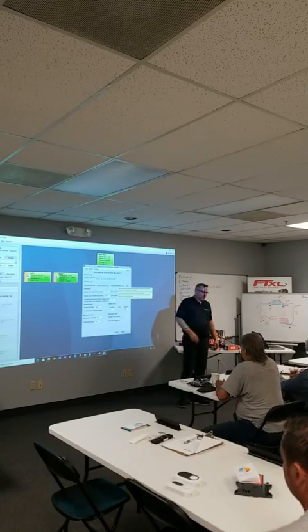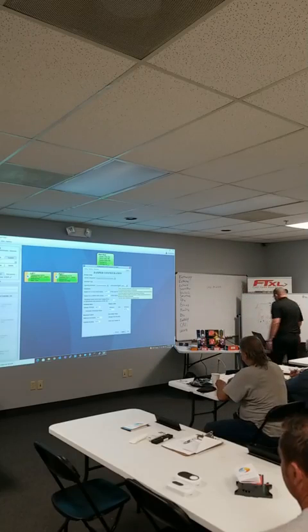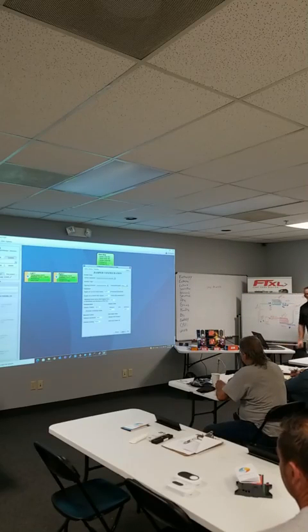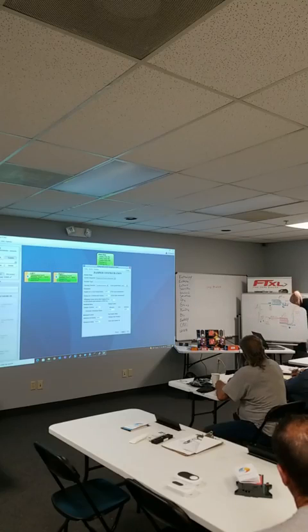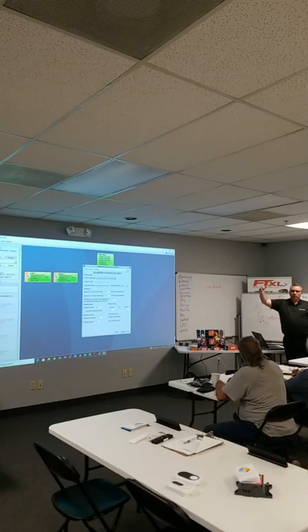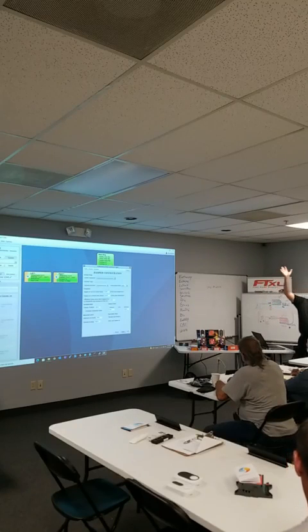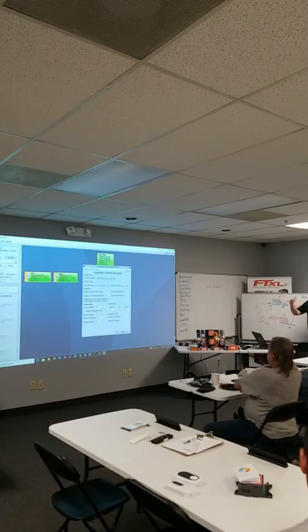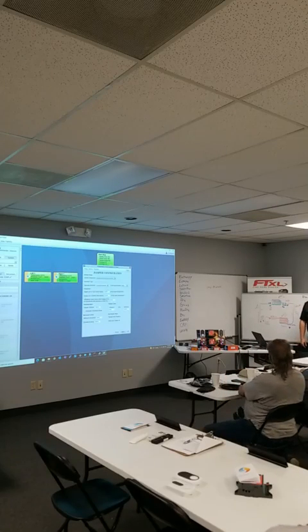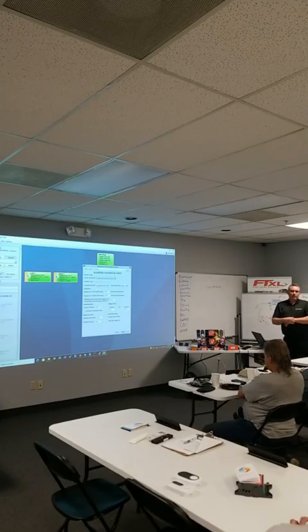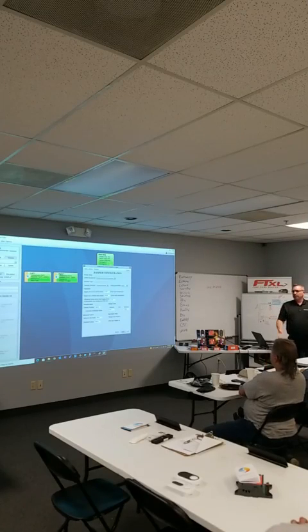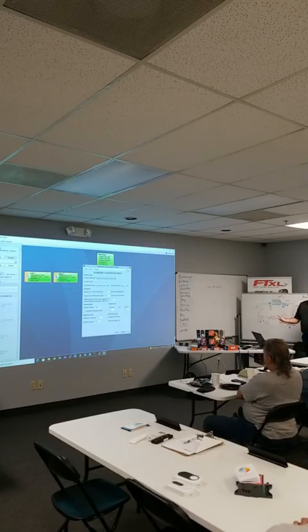We've got the changeover piece, basically saying what the temperature is of the air coming down the duct, and when I'm going to allow the damper to open or close based on my space temperature compared to the temperature in the duct. Right, if I need cooling, is it... I don't mean to cut you off. Oh, go ahead. Is 0.9 the default setting? Yeah, there are a lot of people who use our default. Do some people change them?